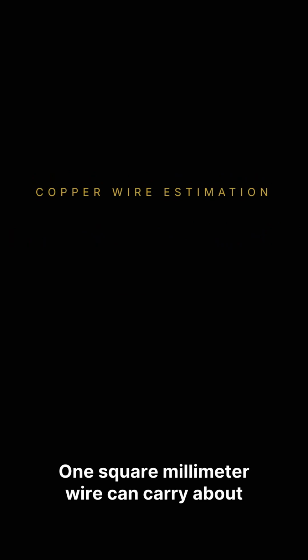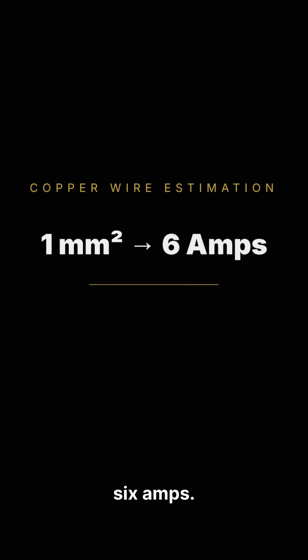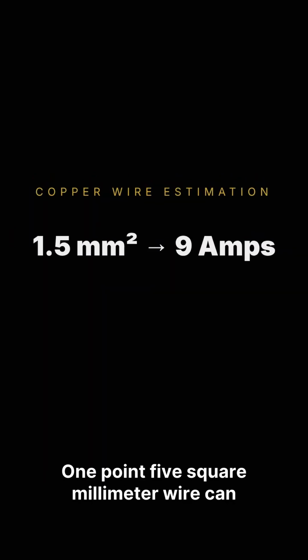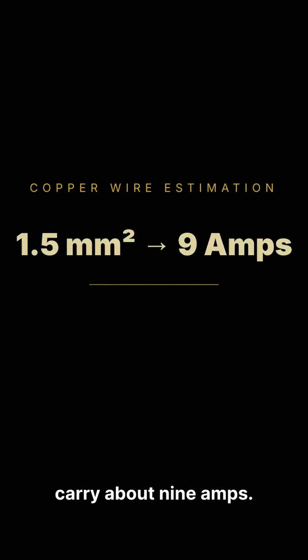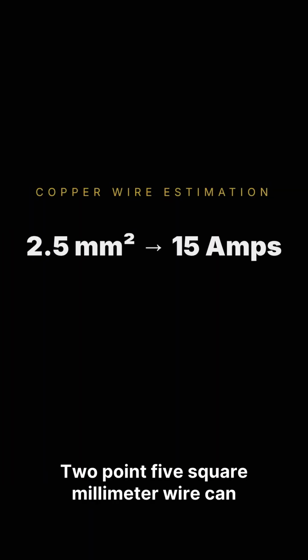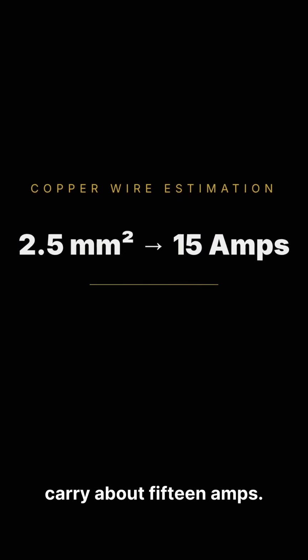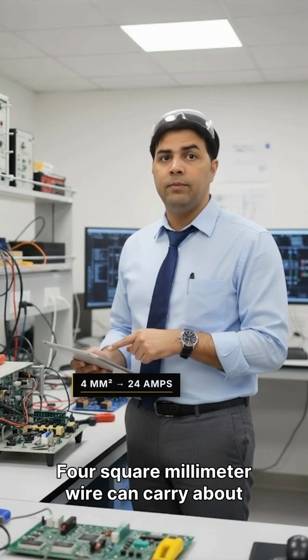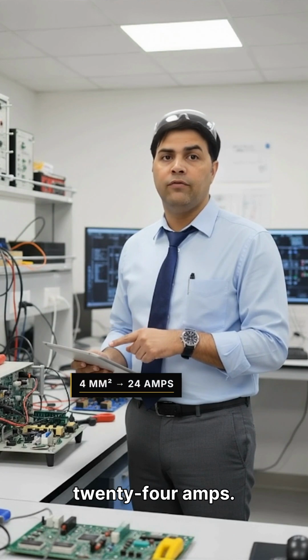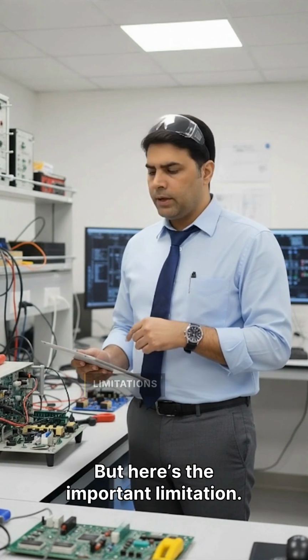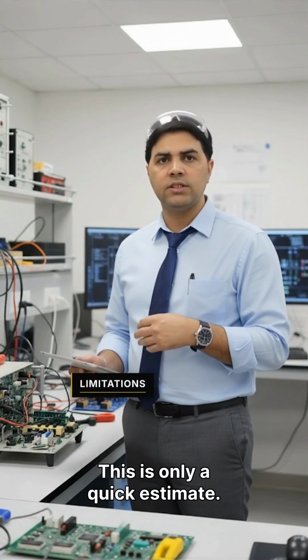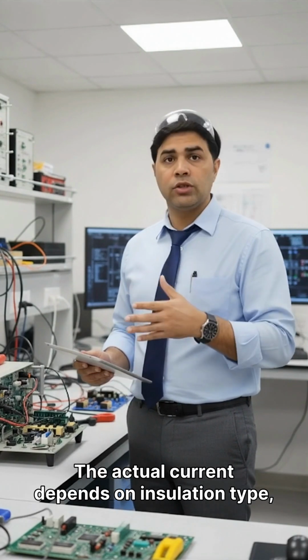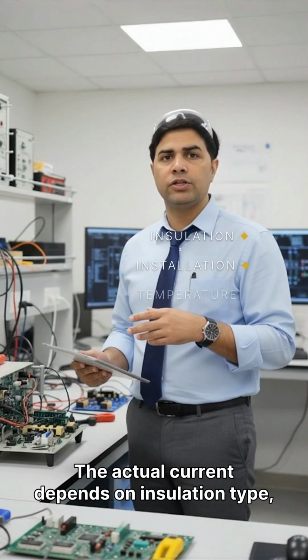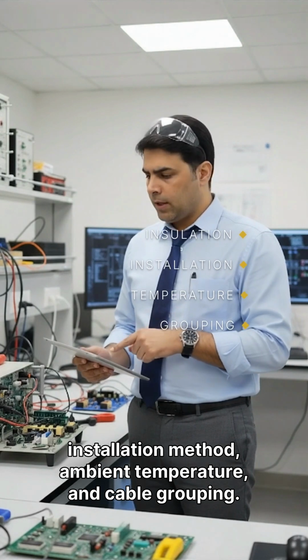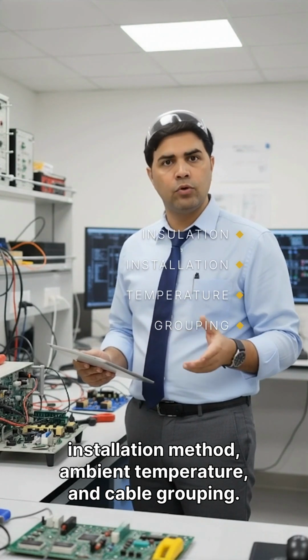1 square millimeter wire can carry about 6 amps. 1.5 square millimeter wire can carry about 9 amps. 2.5 square millimeter wire can carry about 15 amps. 4 square millimeter wire can carry about 24 amps. Simple, isn't it? But here's the important limitation. This is only a quick estimate. The actual current depends on insulation type, installation method, ambient temperature, and cable grouping.